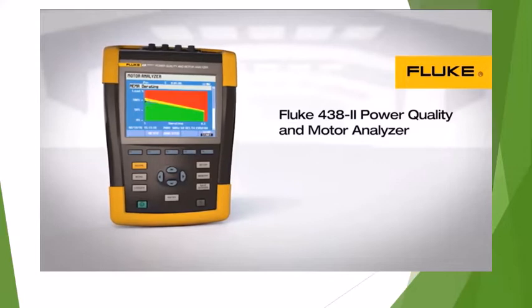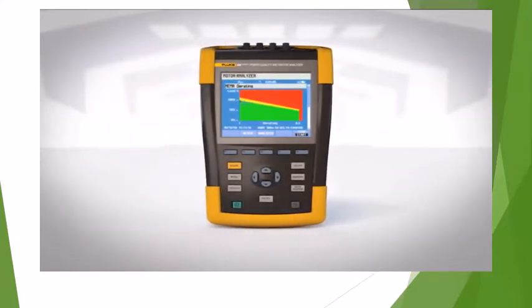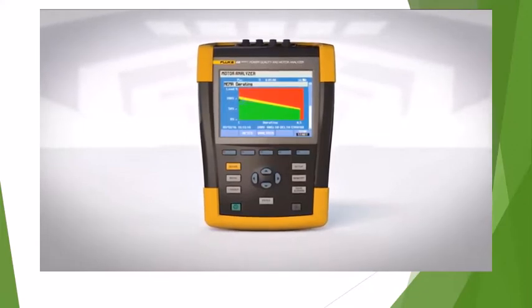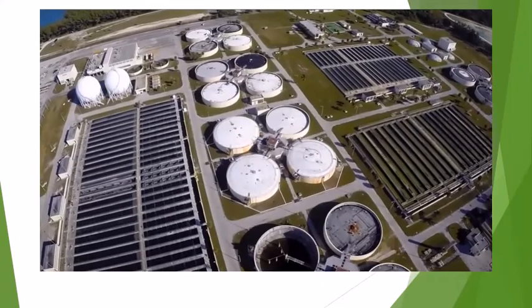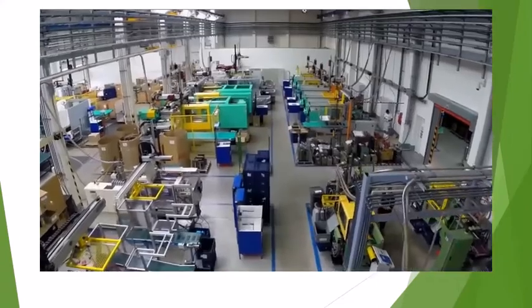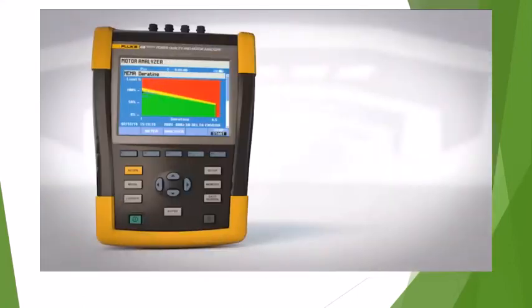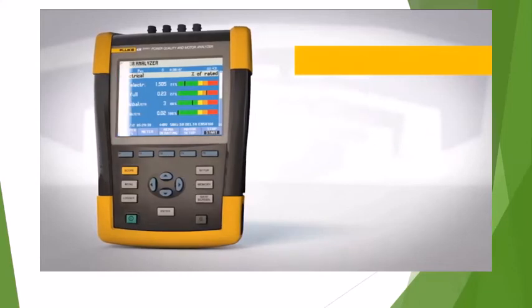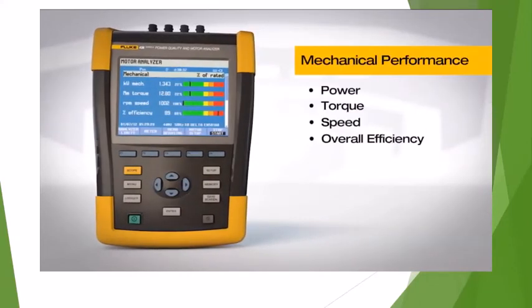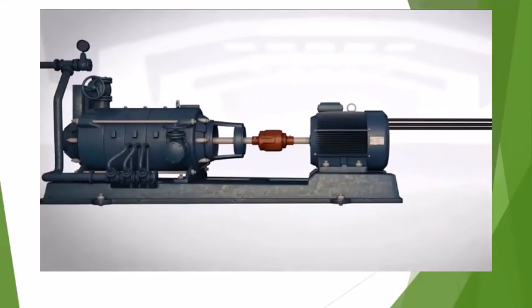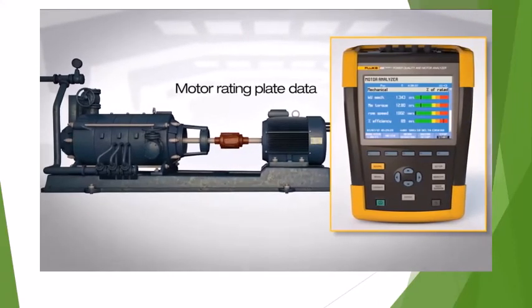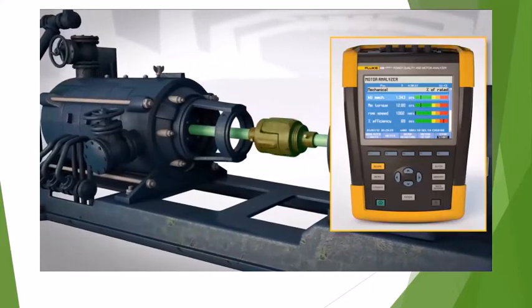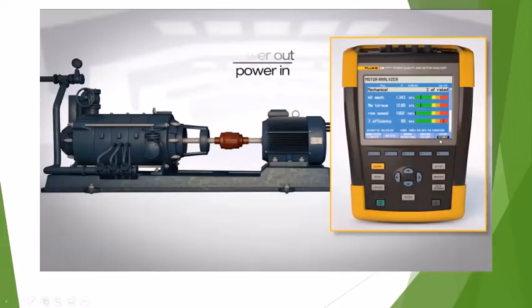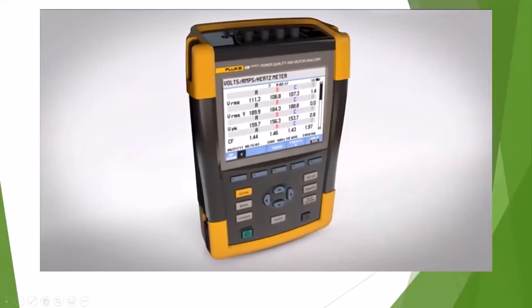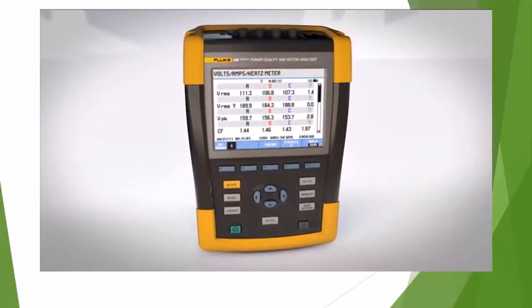Introducing the Fluke 438 Power Quality and Motor Analyzer. The Fluke 438 is a multi-purpose test tool designed to improve troubleshooting on electric motors and minimize downtime. Whether you're in a process plant or discrete manufacturing, electric motors are critical to your operation's success. The Fluke 438 lets you quickly gauge electrical performance, power quality, and mechanical performance of industrial motors. Using three-phase electrical measurements on the input and motor rating plate data, the 438 calculates torque, the most critical mechanical performance variable, speed, load on the motor shaft, and overall efficiency without the need to install mechanical sensors. All this with a single tool, and all while the motor is running so you don't sacrifice uptime.